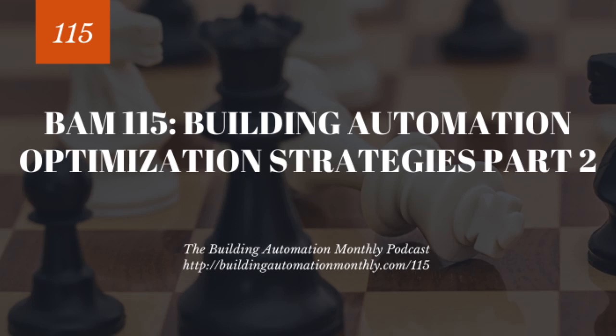So the rule of thumb is two-thirds down the duct, right? You want to put your DP sensor two-thirds down the longest duct run. And that's all well and good. But what if down the longest duct run is actually a really poor sampling of boxes? What if most of your boxes are, I was about to say 10,000 CFM, that'd be huge, are 1,000 CFM, and your box or boxes that are by your DP sensor are 200 CFM.